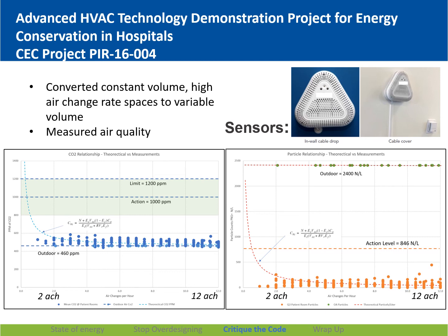If this surprises you, think about it this way. You're wearing a shirt, and before you wear that shirt again, you're going to wash it. You can wash it one time, and it'll be clean enough to wear again. Now, you could continue to wash it. You could wash it 5 times or 10 times or 30 times, and it'll still just be clean enough to wear again. It really doesn't get any better than clean enough to wear again. It's the same with air quality. We don't need a whole lot of air for hygiene, right? We need 1 air change, maybe 2 air changes tops, right? That's all you need for contamination control and air quality. So our cooling systems are often going to take us up to 6 or 10 or 12 air changes, but that's not making the air a whole lot cleaner.